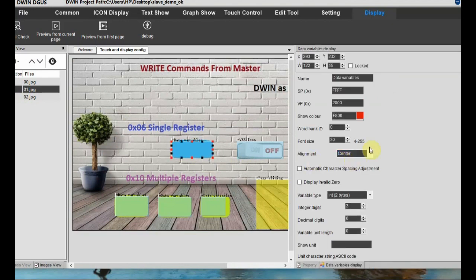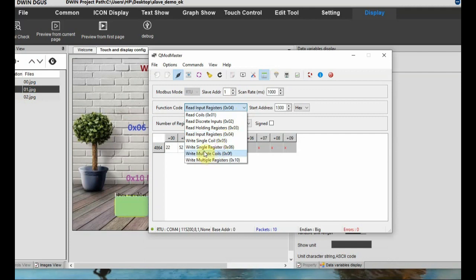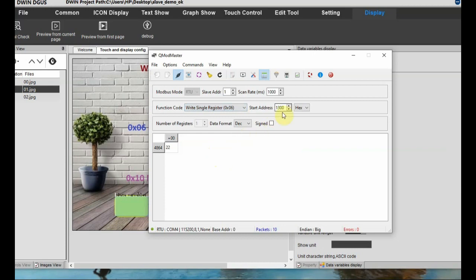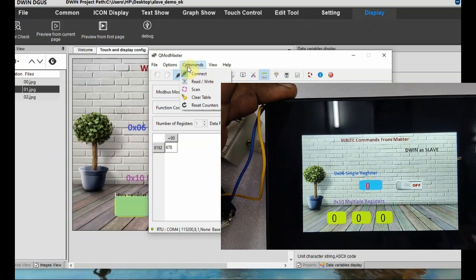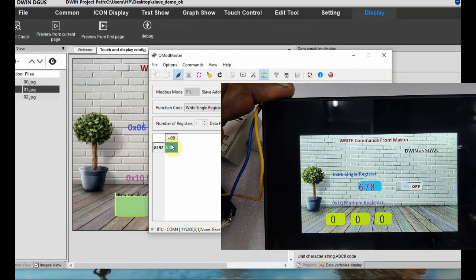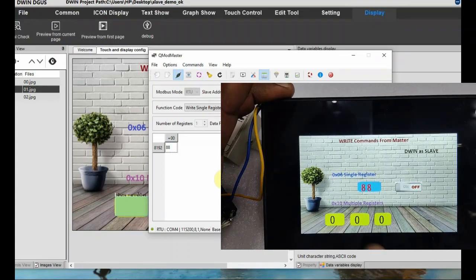Next we will see the write commands from master. For testing the 0x06 command for single register, we use a data variable at VP location 2000 and a variable icon at VP2050. Note that write single coil and write multiple coil are not possible from this simulator. Select write single register 0x06, start address VP2000, number of registers 1, and feed in the value. Click Read/Write - the data will be written to the DWIN slave.